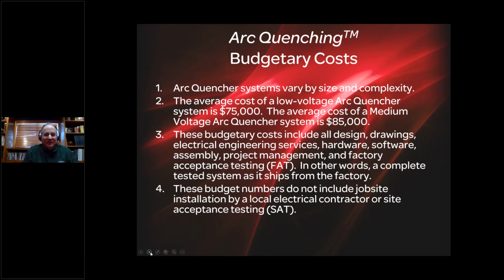People always ask, if I don't mention it, about budgetary cost for arc quenching. What we give people is $75,000 for low voltage systems, and add another $10,000 for medium voltage systems. Again, it's like asking how much does switchgear cost. It's nice to have some criteria, but for budgetary numbers, you will generally be very safe using those numbers when budgeting arc quencher systems. And that includes the hardware, the software, the drawings, the design, the project management, factory acceptance testing, a delivered system working for the application out of the factory, everything except the site acceptance testing.